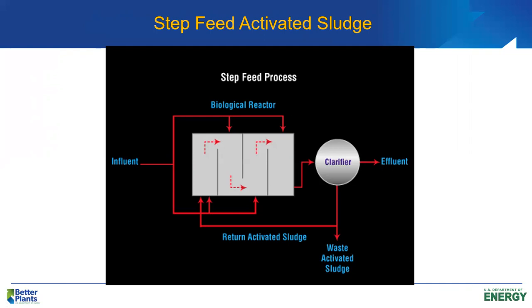In a step feed process operating in step feed mode, we typically have four compartments provided by baffling in the basin. We can bring in one-fourth of the influent to each compartment. This smooths out the organic loading on the reactor. Importantly, the return activated sludge is always brought back to the front of the reactor — it's the influent that is distributed at different points along the reactor.